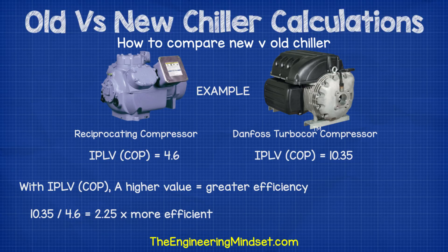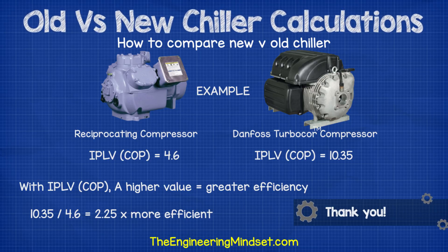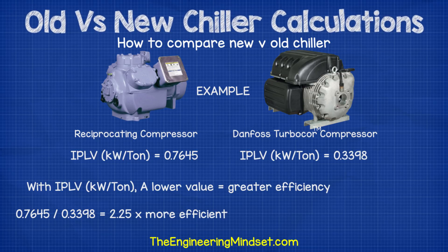There are two types of IPLV values depending on whether it was calculated from the COP/EER or the kilowatts per tonne — these are just slightly different ways to calculate efficiency. For example, a chiller with a reciprocating compressor might have an IPLV COP rating of 4.6, whereas an equivalent Turbocor compressor might have an IPLV COP rating of 10.35. A higher COP means a more efficient chiller, so the Turbocor is more efficient. When rated on IPLV kilowatts per tonne, a lower value means more efficiency — the reciprocating chiller might be 0.7645 kW/tonne whereas the Turbocor might be 0.3398 kW/tonne, again confirming the Turbocor is more efficient.